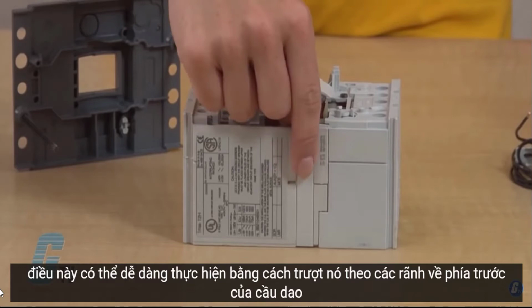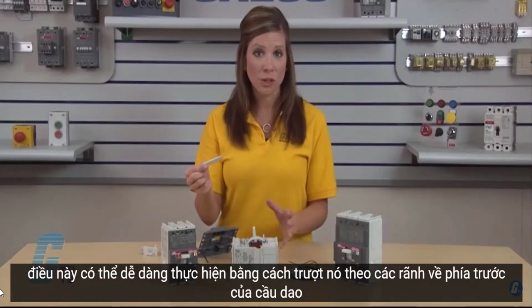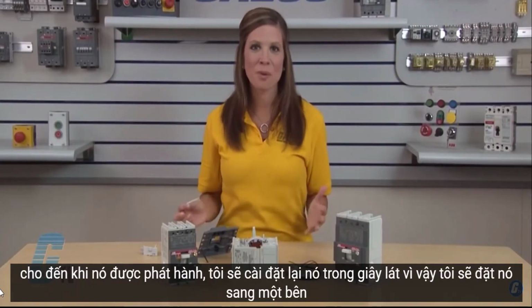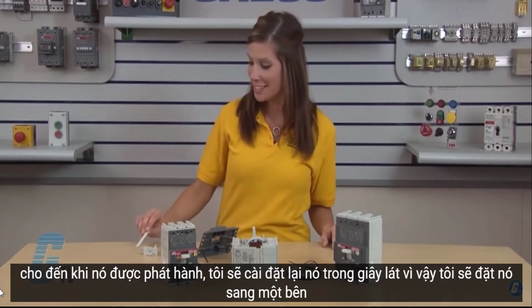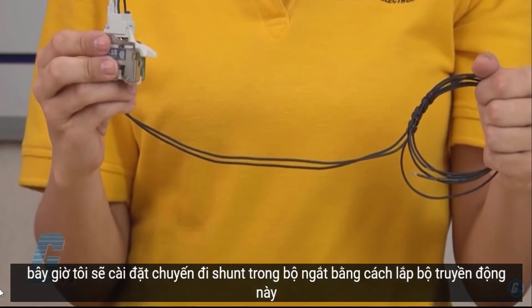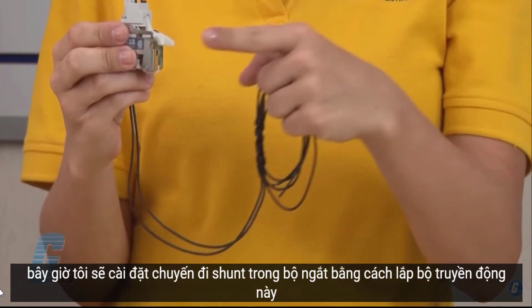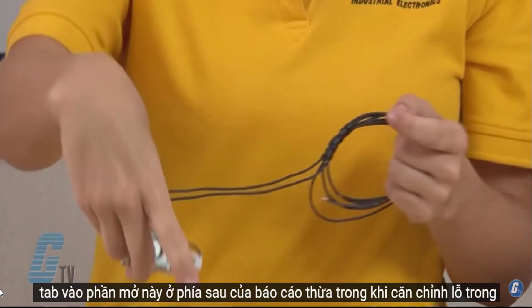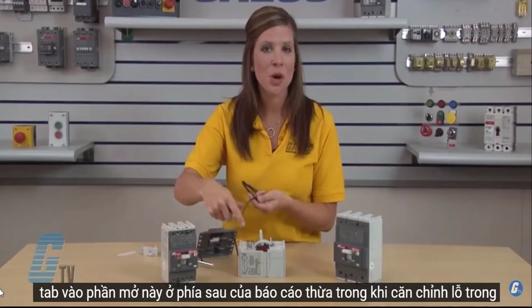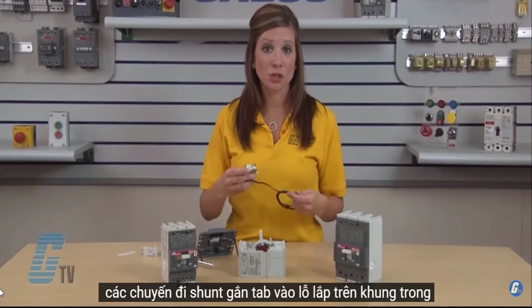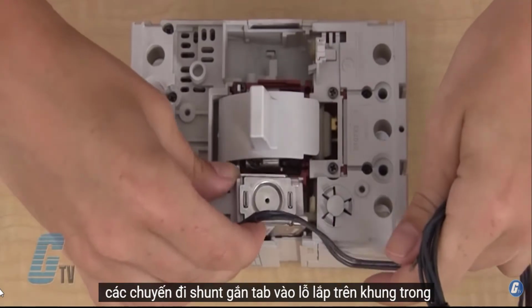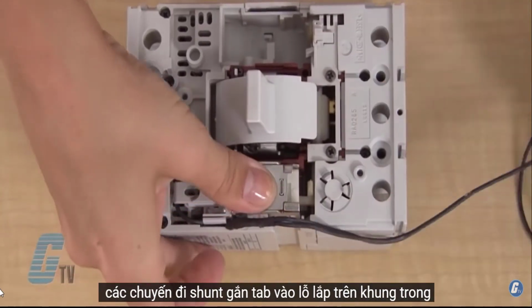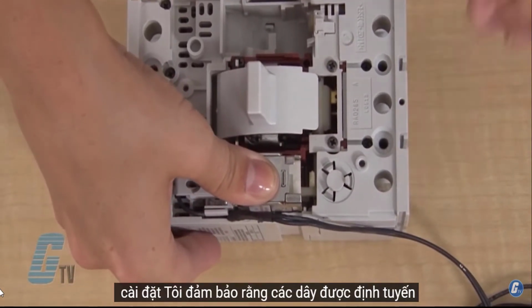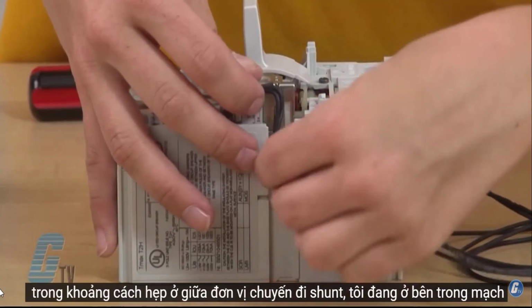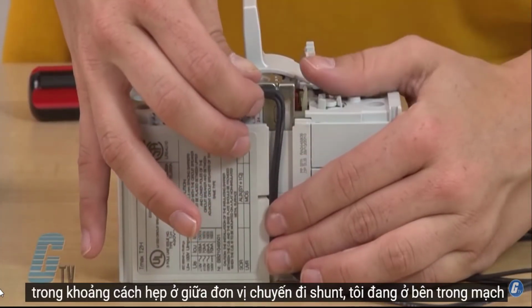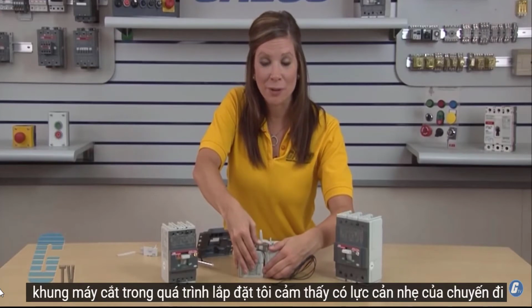This is easily done by sliding it in the grooves towards the front of the breaker until it is released. I will reinstall this in a moment, so I will set it aside for now. I will install the shunt trip in the breaker by inserting this actuator tab into this opening at the back of the accessory port, while aligning the hole in the shunt trip's mounting tab into the mounting hole on the frame. During the installation, I carefully make sure that the wires are routed in the narrow gap in between the shunt trip unit and inside of the circuit breaker frame.